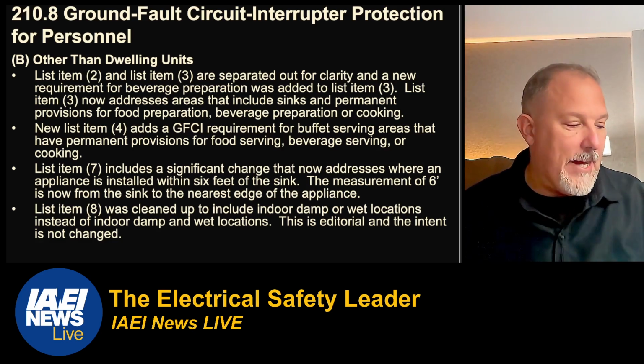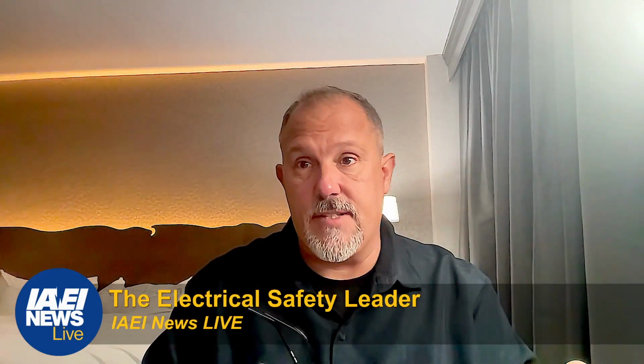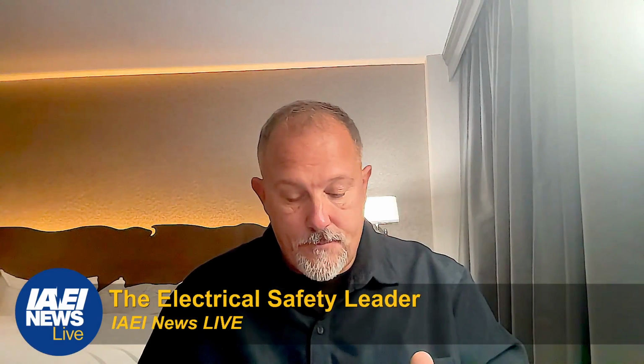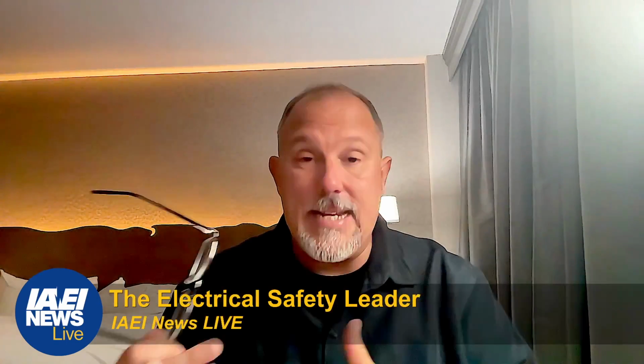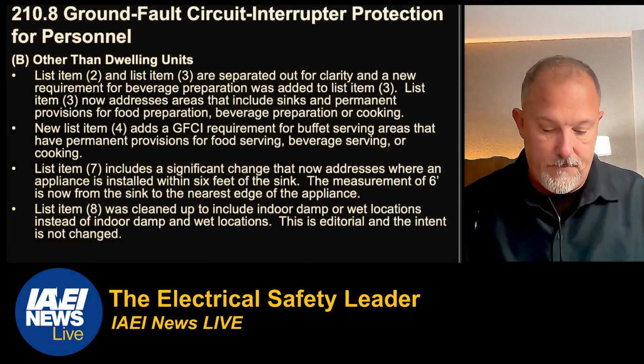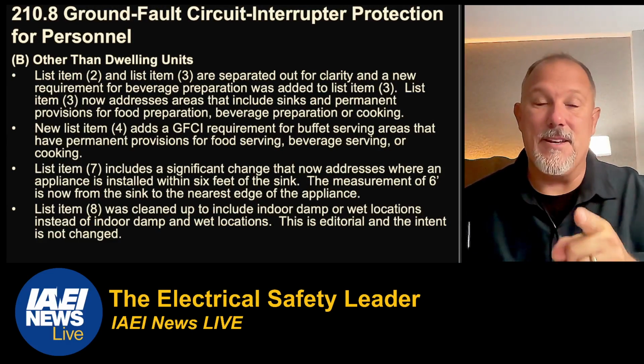So the discussion that we had at Code Panel 2 was around the fact that the hazard is not the receptacle. That's just a measurement method to identify what needs to be GFCI protected and what doesn't. The hazard's really around the appliance. So what we did in B was we said, look, sinks where receptacles are cord and plug connected, fixed or stationary appliances are installed within 6 foot. So it's not the receptacle; the receptacle could be 7 feet away from the sink, but if the appliance is within 6 feet of the sink, then you need to GFCI protect it. So we're focusing on the appliances, and this is a lead in to the discussion that we're going to have in a little bit. That's going to be another impact to residential dwelling units.